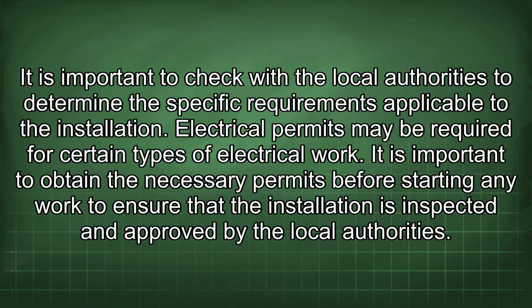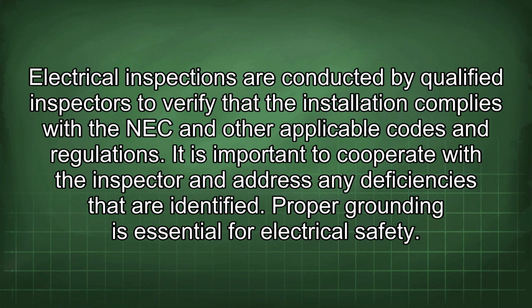It is important to check with the local authorities to determine the specific requirements applicable to the installation. Electrical permits may be required for certain types of electrical work. It is important to obtain the necessary permits before starting any work to ensure that the installation is inspected and approved by the local authorities. Electrical inspections are conducted by qualified inspectors to verify that the installation complies with the NEC and other applicable codes and regulations. It is important to cooperate with the inspector and address any deficiencies that are identified.